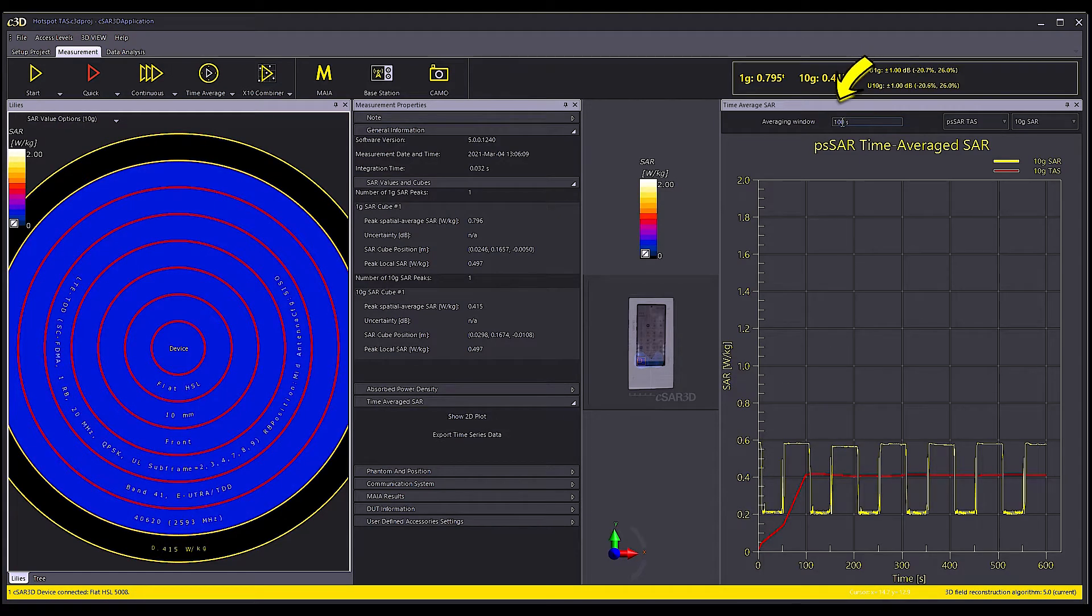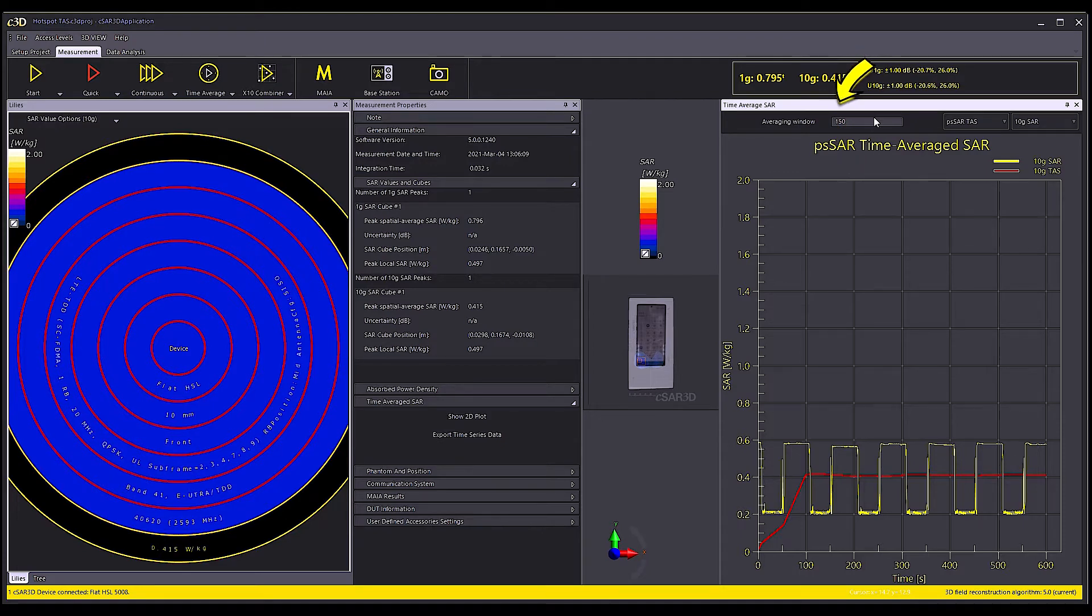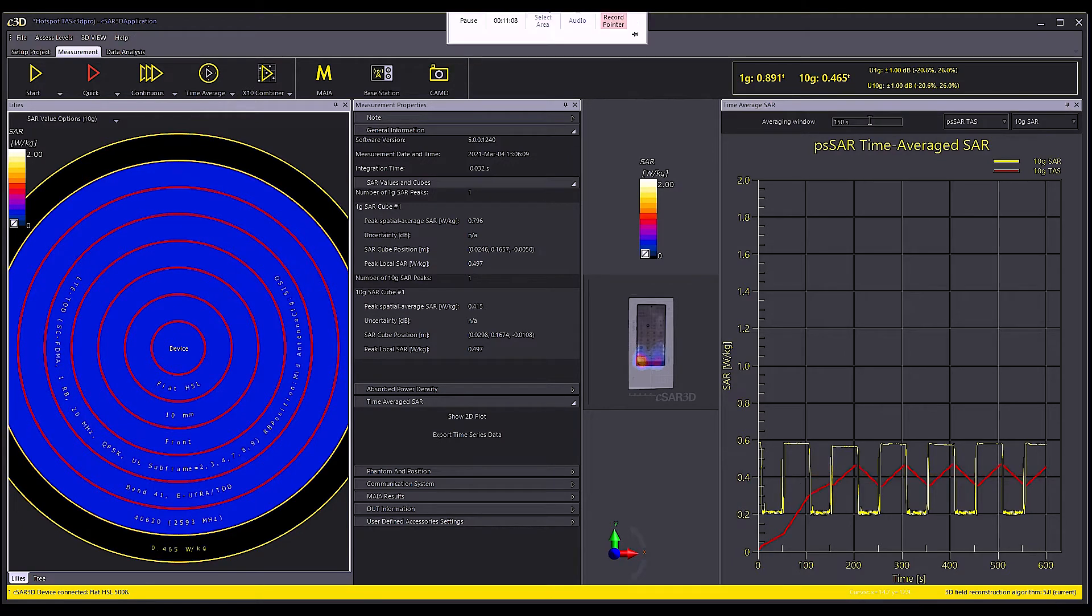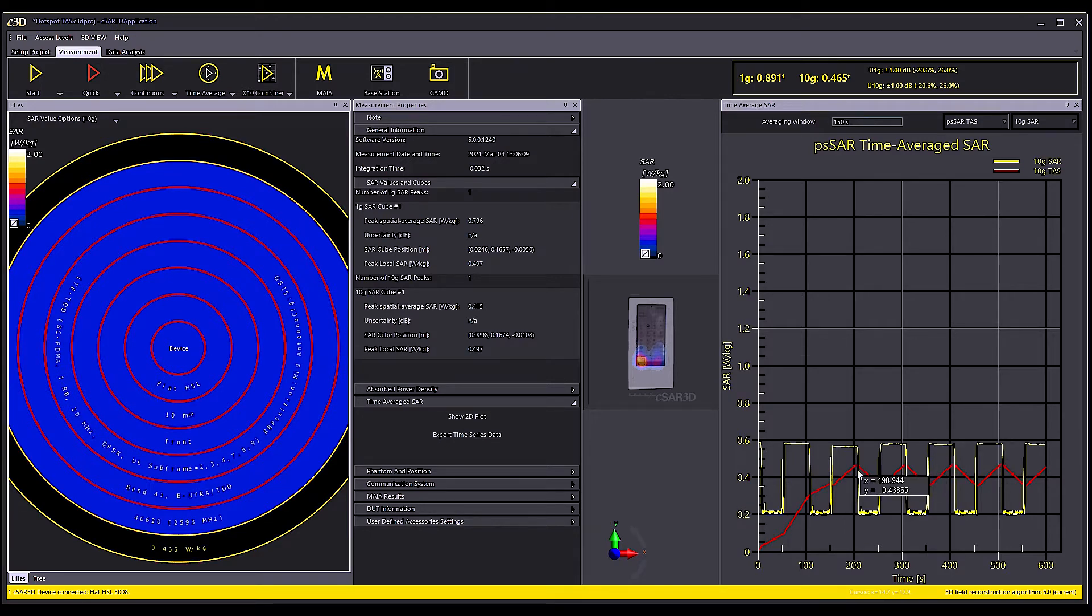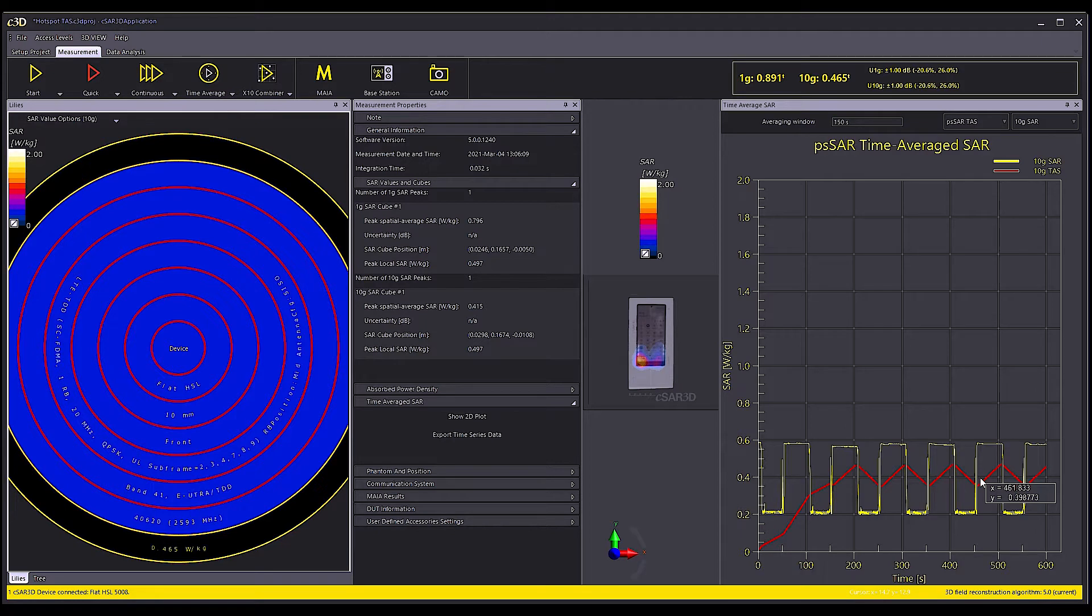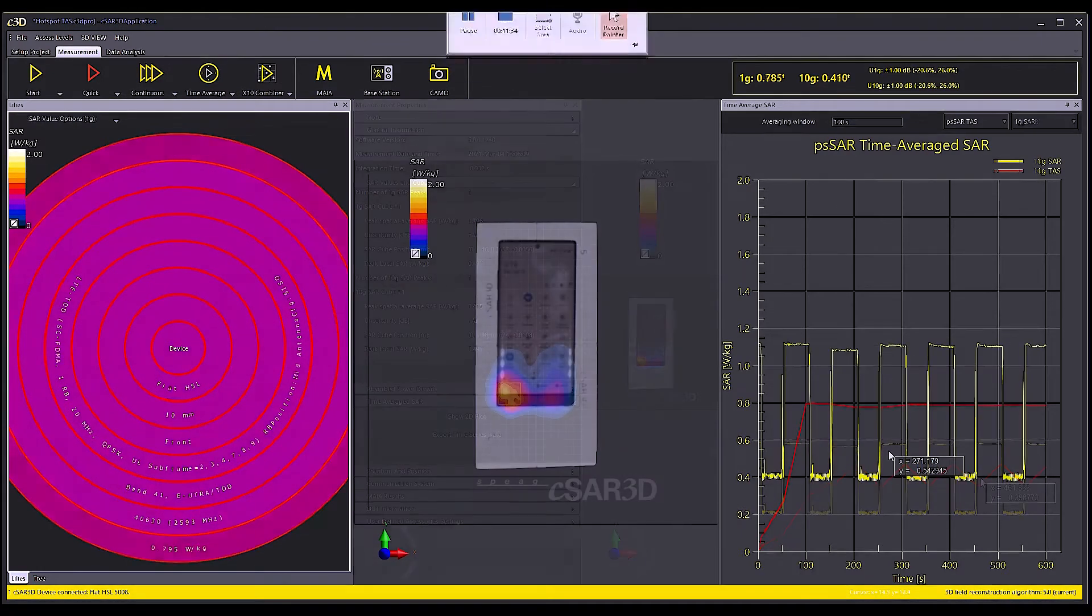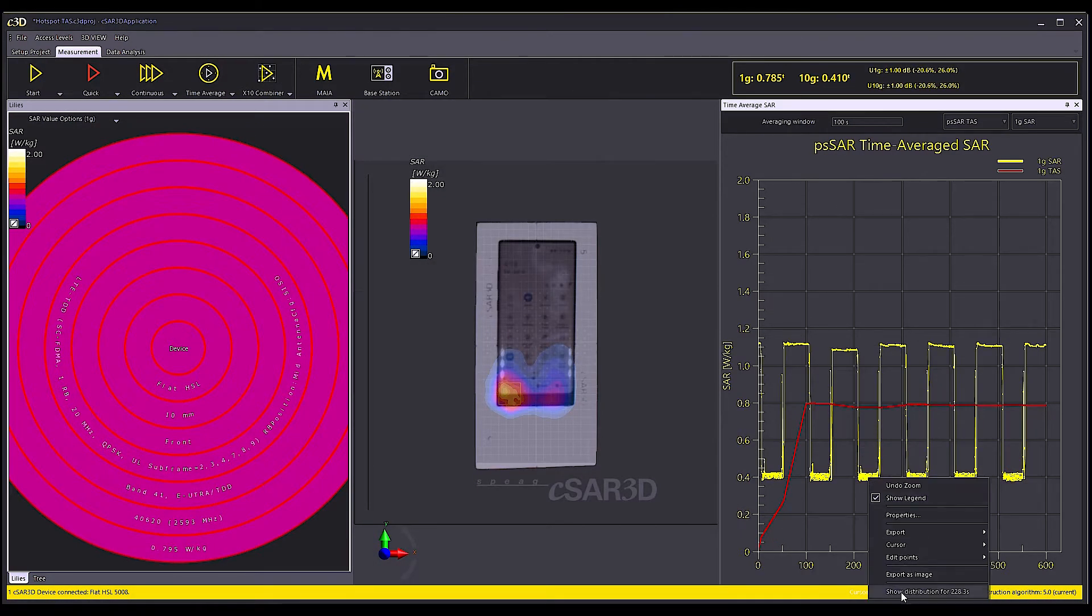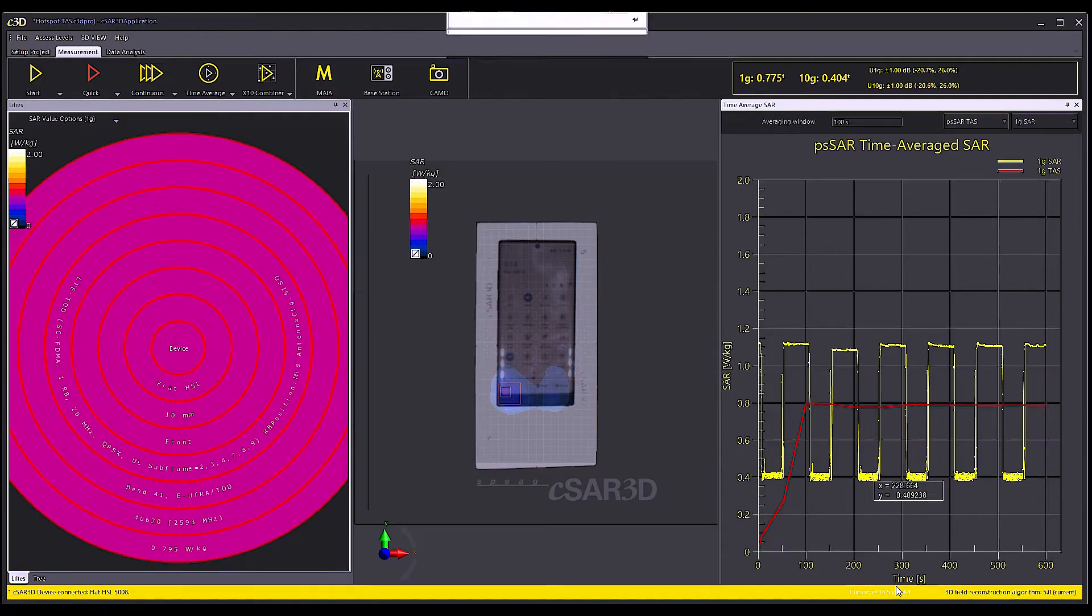Once measurements of TAS are done, these can be re-evaluated for a different averaging window. For instance, I will look at the 10 gram TAS with the averaging window set to 150 seconds. It is also possible to look at the instantaneous SAR pattern for any of the individual measurements through the 2D plot flow distribution option.